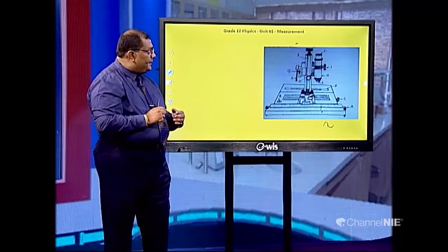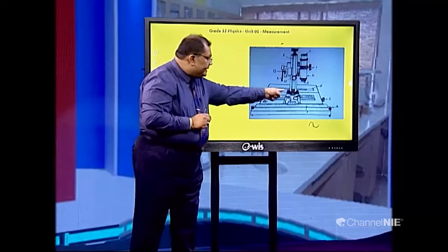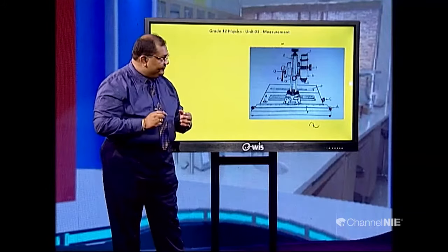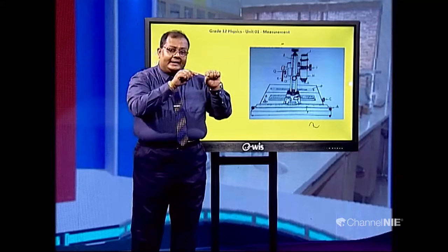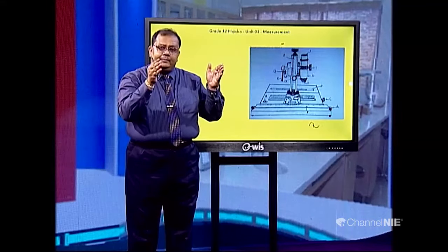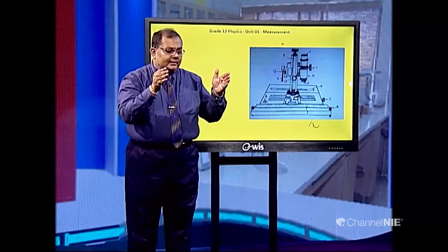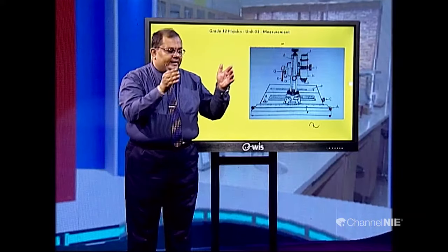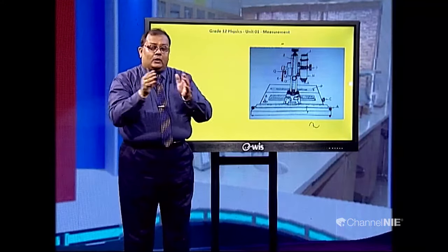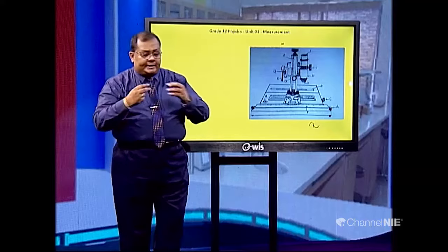Now, a mercury pellet should be inserted into the capillary tube. Normally the length should be 150 millimeters. After that, we are measuring the length of the mercury pellet when it is located at 3 different locations inside of the tube, like this.